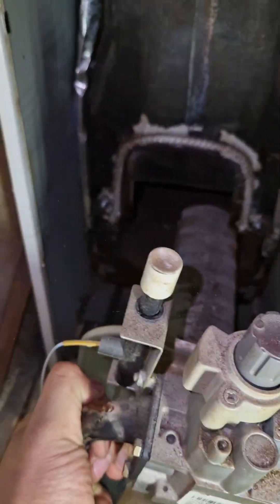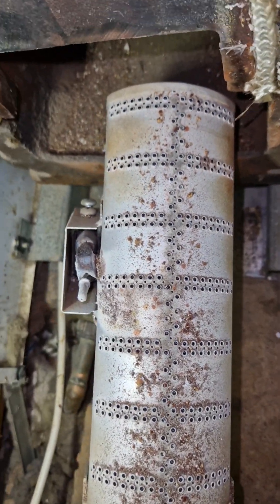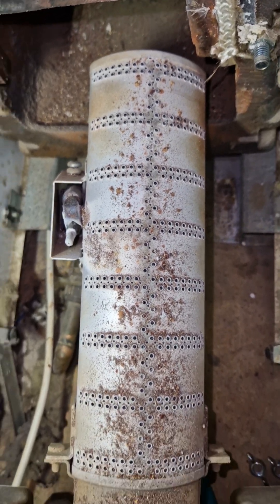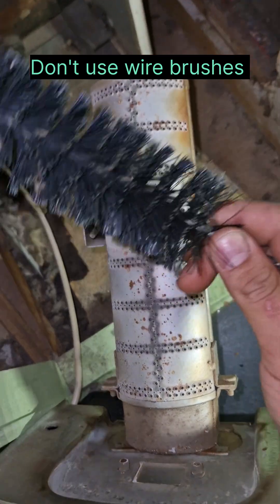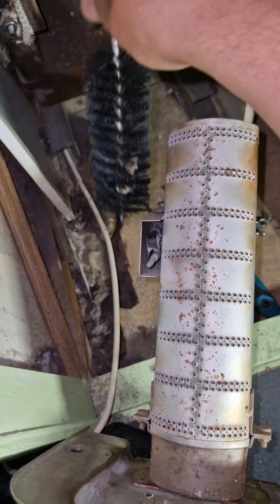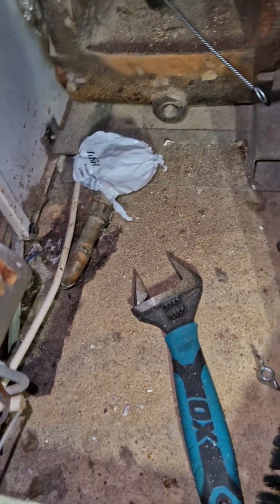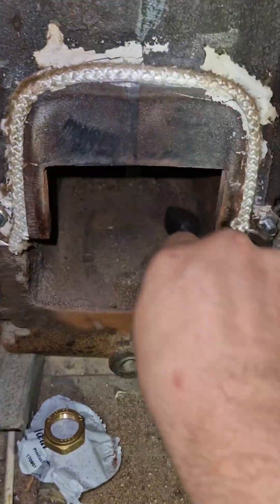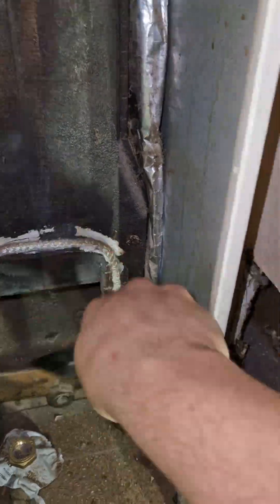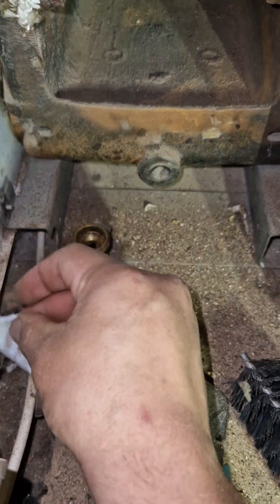Just be careful not to bend anything, especially any wires that might get caught up. What you're looking for on this is to make sure all the holes in the burner look good — you don't want them distorted, you don't want them cracked, you don't want the burner cracked. This is a very light nylon brush, not wire, and it's very soft. Just sweep that up like that.